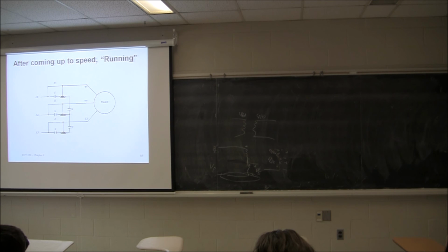So this is a preferred way over a variable frequency drive, because a variable frequency drive is always on, it's always using power. The advantage of a variable frequency drive is you can precisely control the amount of torque output, but sometimes why do you care? If you're just pumping water from point A to point B and you don't care how much water is flowing, then you would just use an auto transformer. It's much, much cheaper.